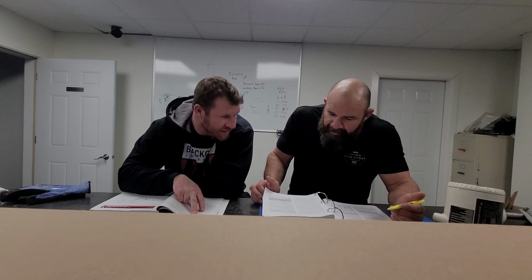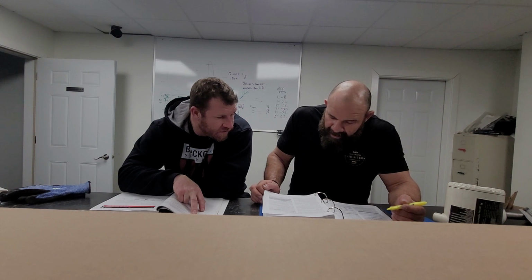Where does it talk about headroom? What does it say? Well, working spaces. The minimum headroom is 6.5 feet. That would make sense. Maybe it's talking about the space equal to the width and depth of the equipment and extending from the floor to a height of 6 feet above the equipment or to the structural ceiling, whichever is lower, shall be dedicated to the electrical installation. Oh, that's why. It's not 6.5. It's 6 feet.